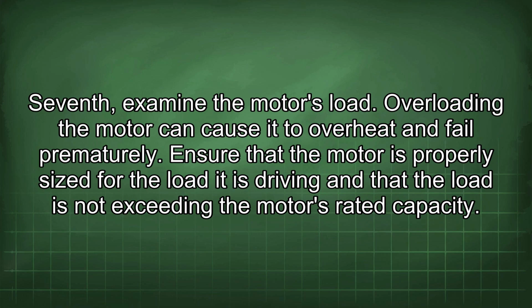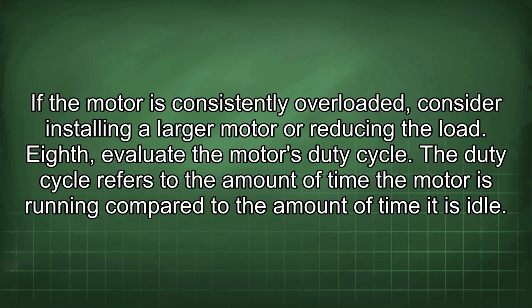Seventh, examine the motor's load. Overloading the motor can cause it to overheat and fail prematurely. Ensure that the motor is properly sized for the load it is driving and that the load is not exceeding the motor's rated capacity. If the motor is consistently overloaded, consider installing a larger motor or reducing the load.